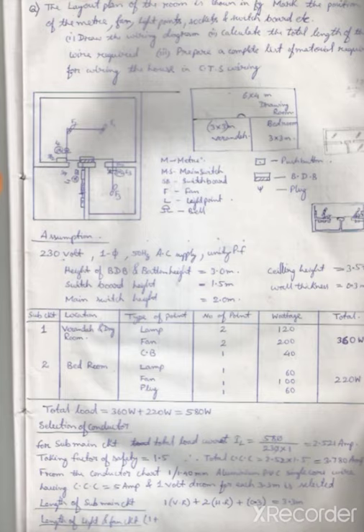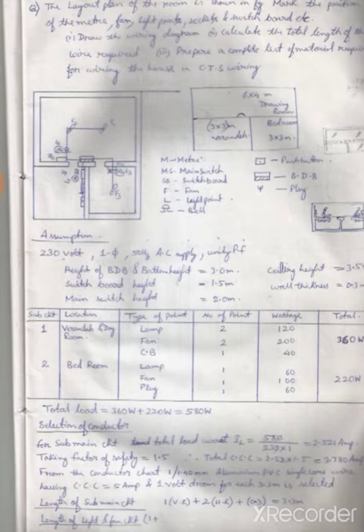Let us divide this circuit into sub circuits with the help of a table. Sub circuit 1: location is veranda and drawing room. Type of point is lamp, fan, and calling bell. Number of points for lamp is 2, each lamp consumes 60 watts, so total is 120 watts. There are two points for ceiling fan, each of 100 watts, total wattage 200 watts. For calling bell, one of 40 watts. Total wattage for sub circuit 1 is 360 watts.